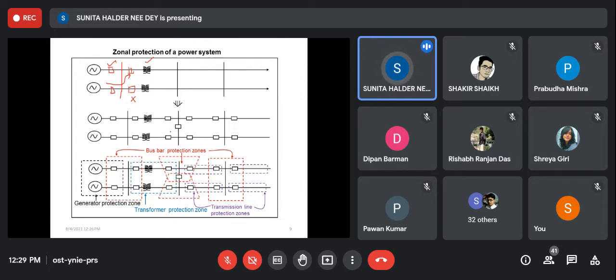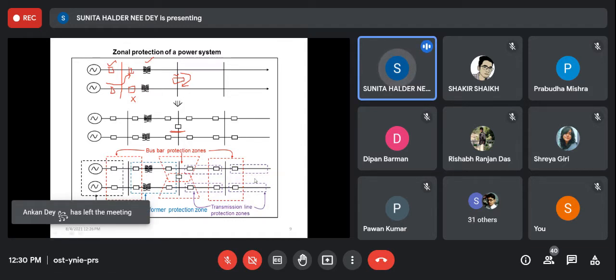You can see in the bus bar also there is subdivision. So that means if there is any short circuit here, if we put a subdivision, a section here, then this fault will not be transferred to the other side. So the purpose of power transfer will be served to some extent. Sometimes it may not be in total, but the purpose will be served. So in the same way, actually, there are so many subdivisions.